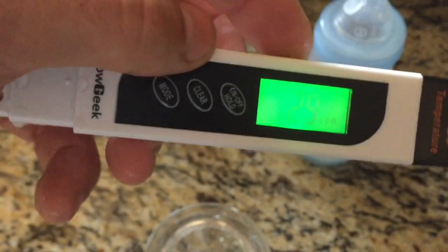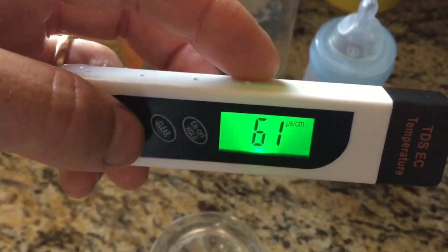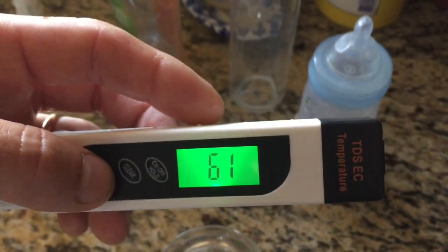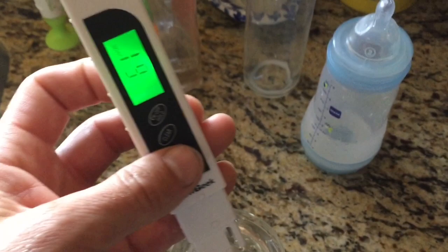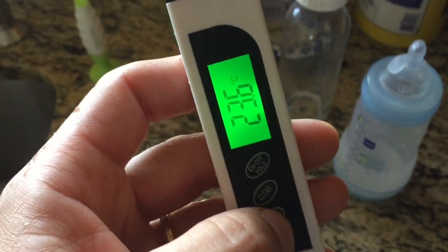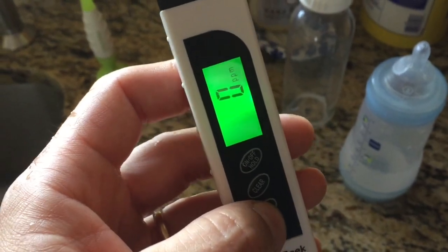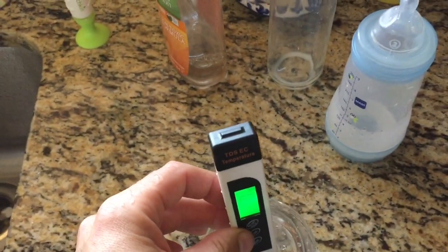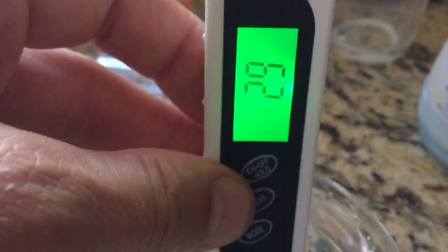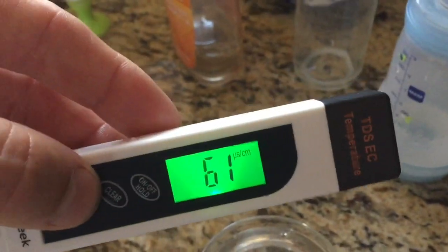After the full rinse period, we got 29 particles per million and 61 electrical conductivity. Confirmed again: 29 particles per million and 61 EC.